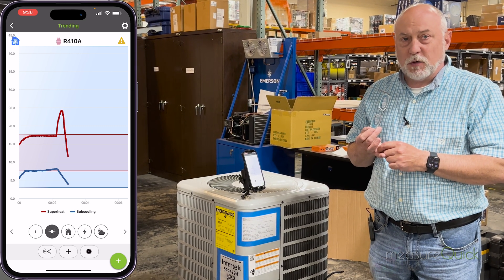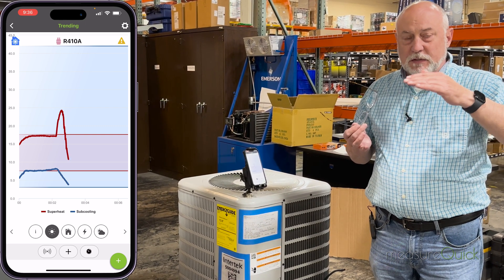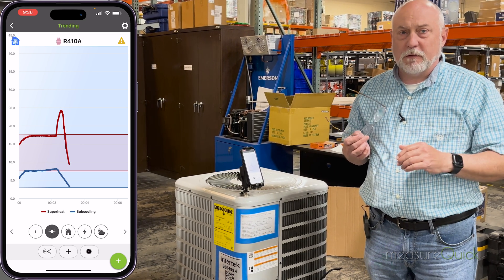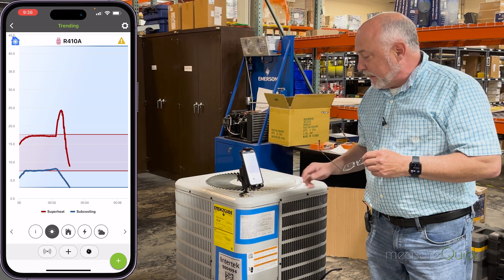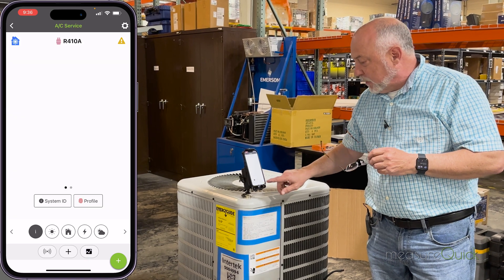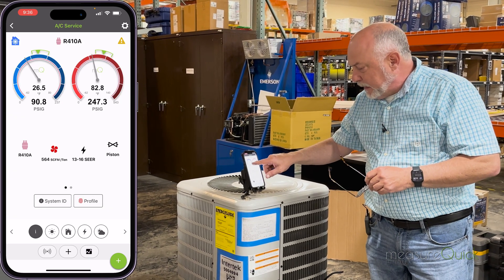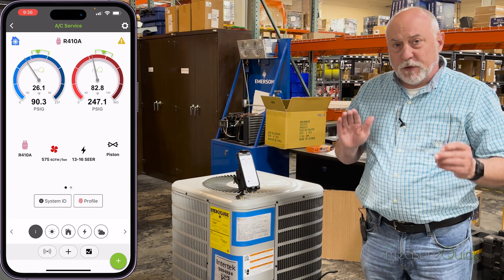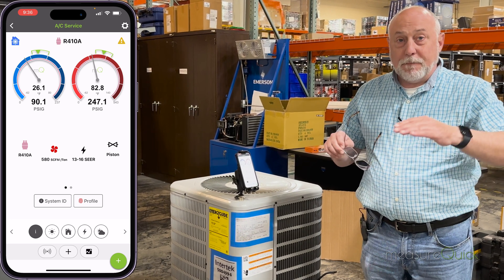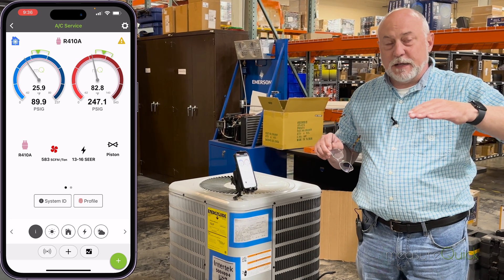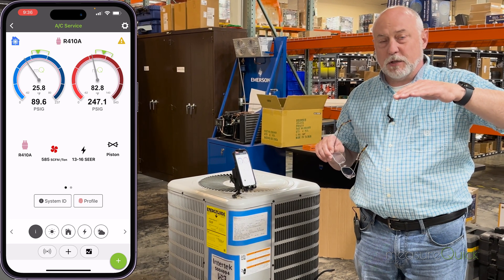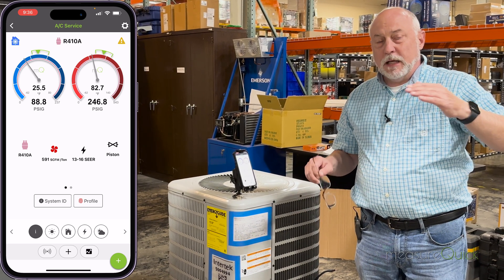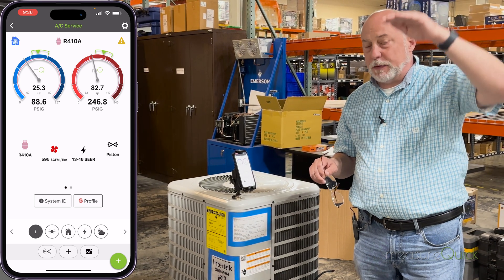What you've got to remember is pressure on a system changes much faster than the line temperatures do. The refrigerant has mass — the refrigerant takes time to cool down once you drop the pressure on it. The pressure is going to change very quickly. What's effectively happening is the saturation temperature, the pressure, is dropping down very, very quickly. We're at a 26-degree coil right now. Pressure changed very quickly; refrigerant temperature did not. So the superheat calculation shows really high superheat for a moment because the saturation temperature went really low while the suction line temperature is still high.